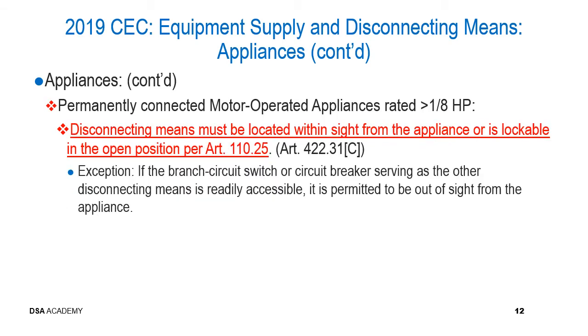The third condition relating to appliances that are permanently connected is permanently connected motor-operated appliances rated over 1/8 horsepower. And this verbiage is a new amendment to the 2019 version of the California Electrical Code, and it states that the disconnecting means must be located within sight from the appliance or is lockable in the open position per Article 110.25.